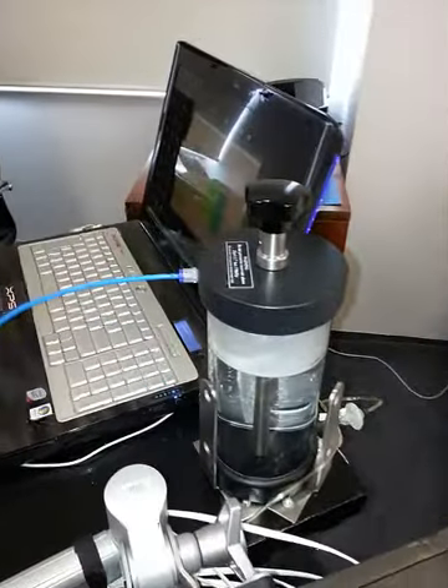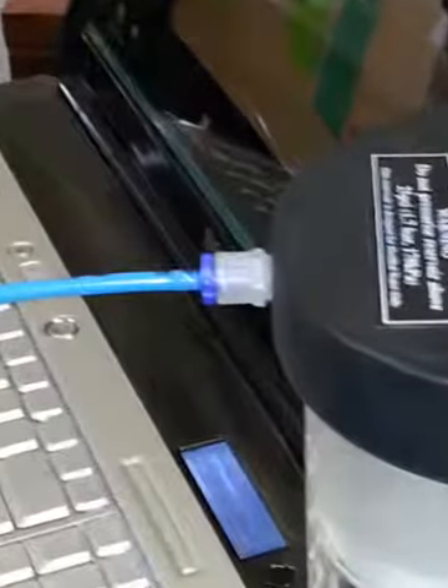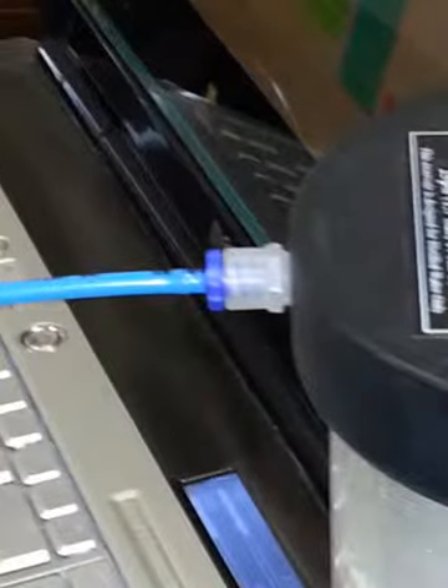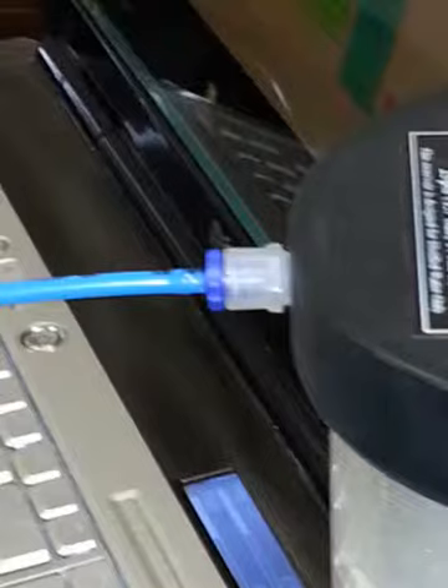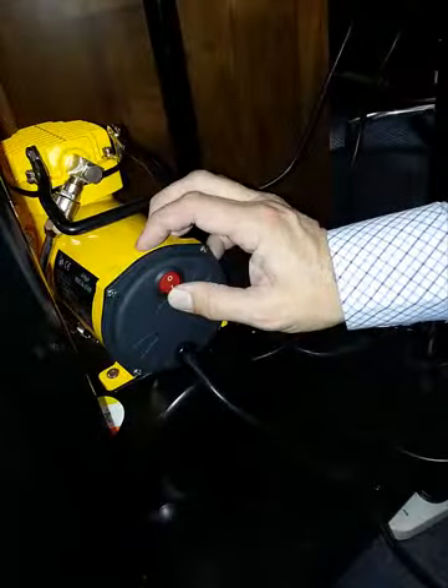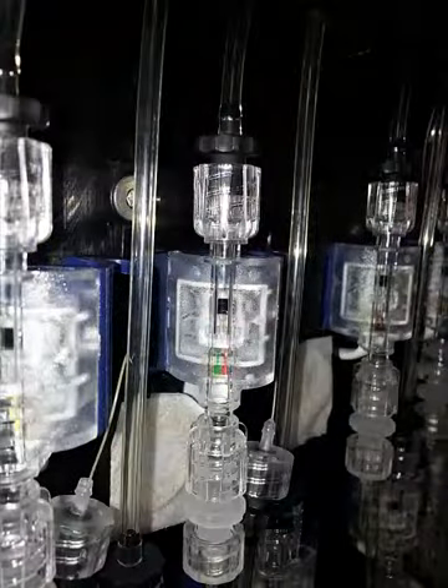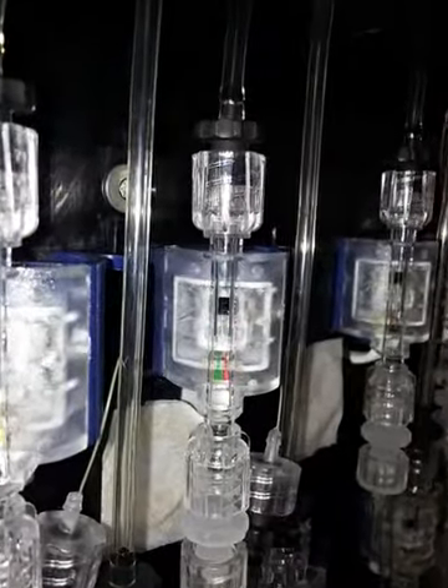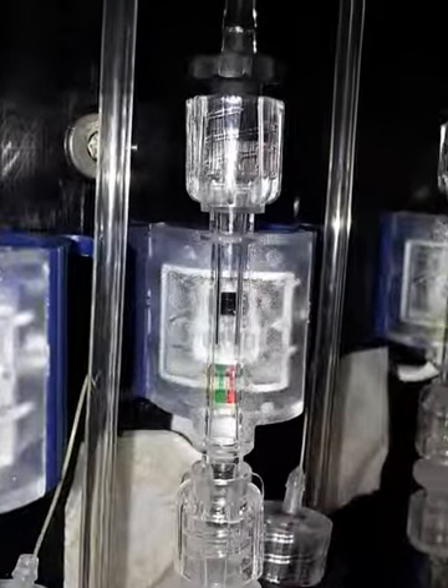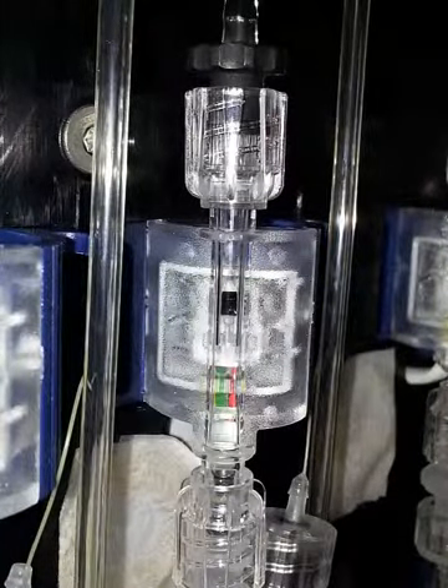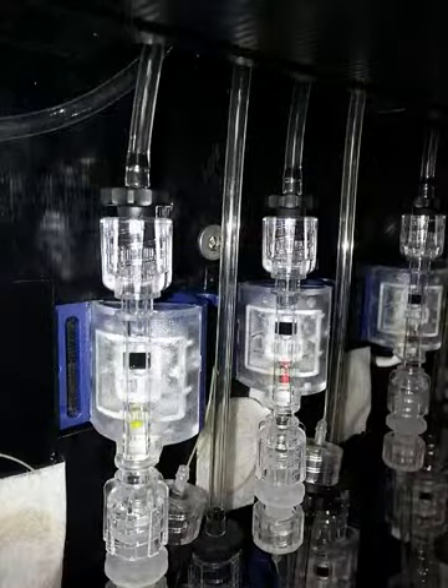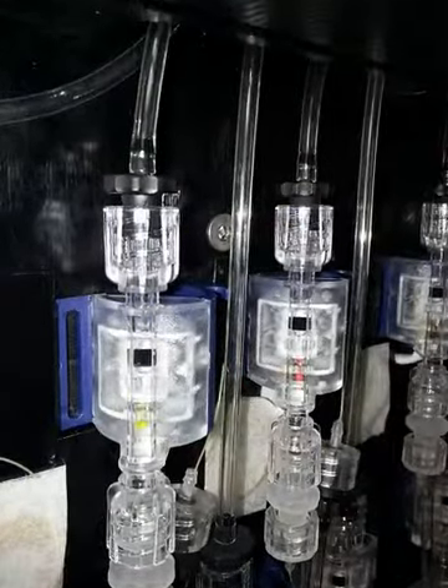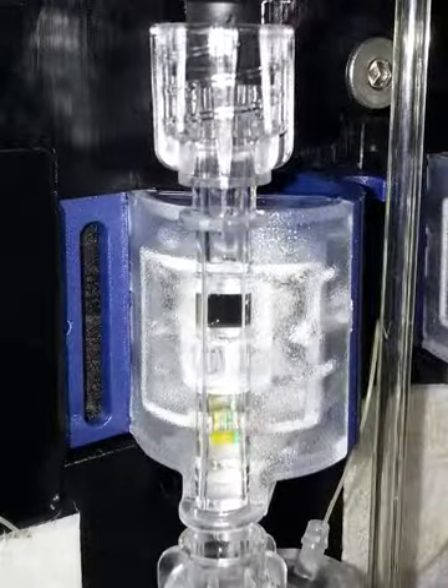Now attach the blue air pressure line to the inlet of the water reservoir and pressurize the reservoir by either opening the valve on a compressed air cylinder or turning on the air compressor. Water should now start perfusing up through the capillaries and into the transducer chambers. The transducer membranes change in appearance as the chamber fills with water, appearing to become larger and blacker.